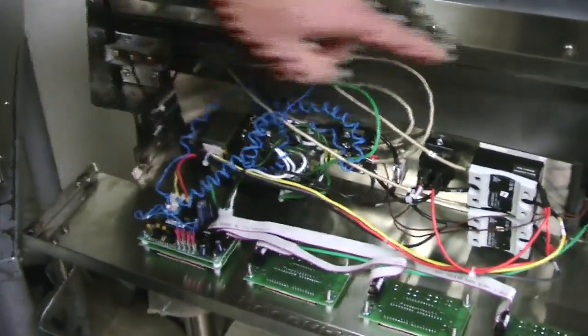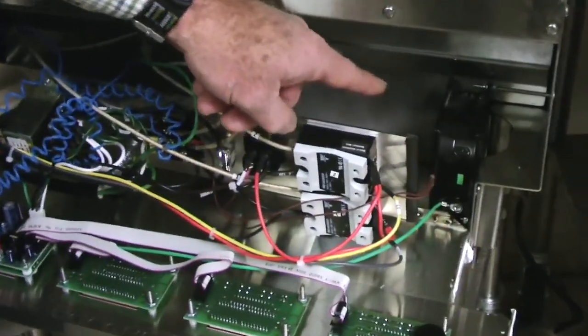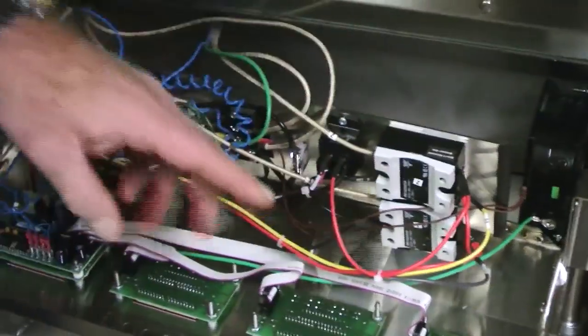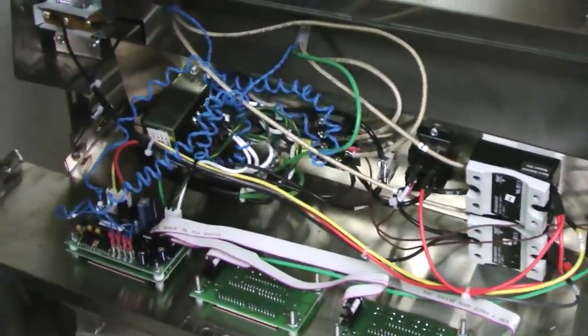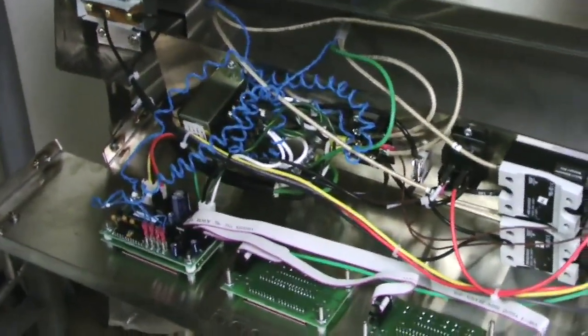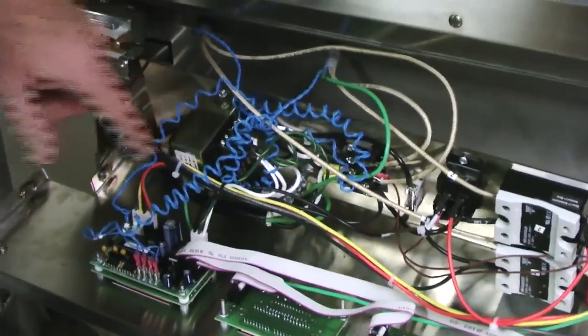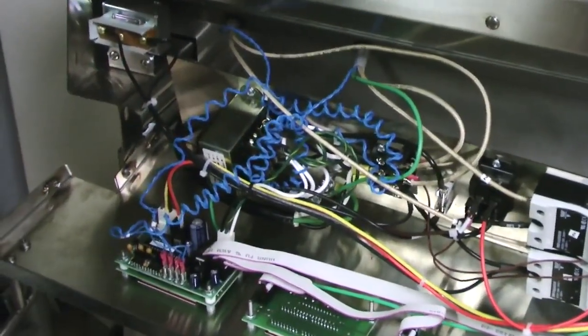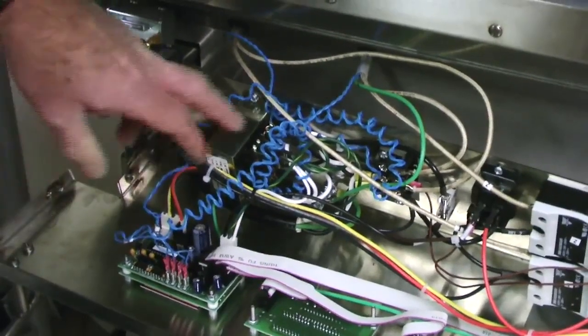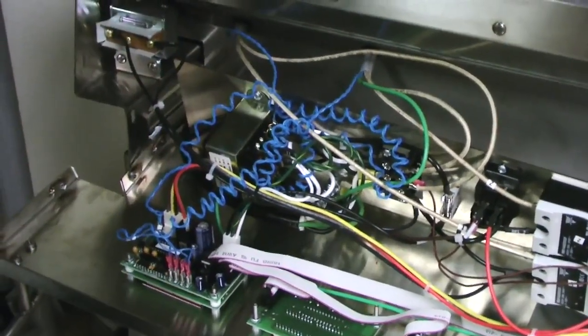This would control the fan, relays, lighting, all that bit. So it could be a situation where that transformer's gone and you check the voltage on the transformer to see if you're getting 12 volts, to ensure that it's not a downed transformer.